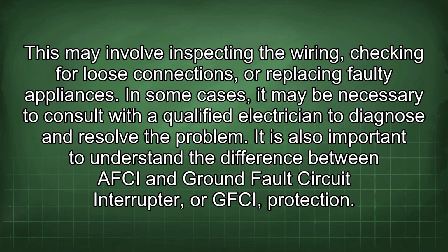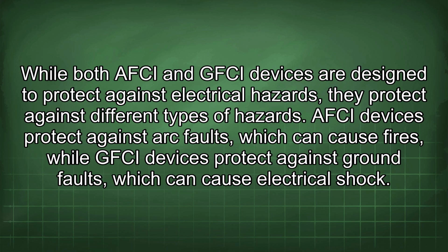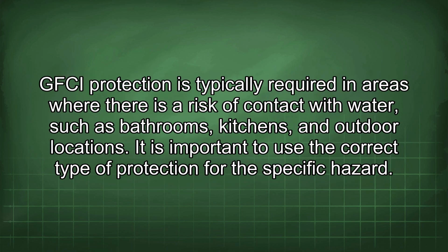It is also important to understand the difference between AFCI and ground fault circuit interrupter, or GFCI, protection. While both AFCI and GFCI devices are designed to protect against electrical hazards, they protect against different types of hazards. AFCI devices protect against arc faults, which can cause fires, while GFCI devices protect against ground faults, which can cause electrical shock. GFCI protection is typically required in areas where there is a risk of contact with water, such as bathrooms, kitchens, and outdoor locations. It is important to use the correct type of protection for the specific hazard.